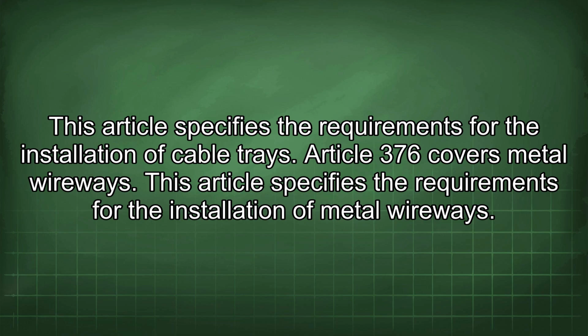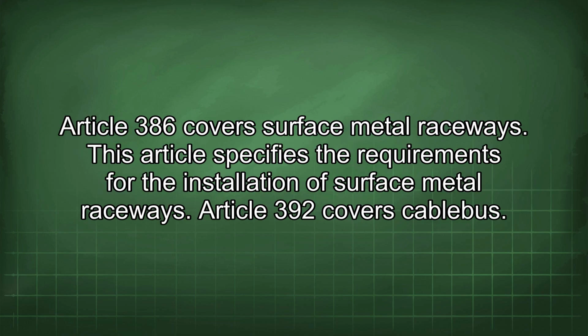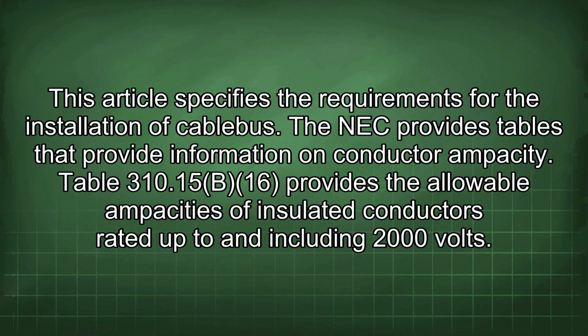Article 376 covers metal wireways. This article specifies the requirements for the installation of metal wireways. Article 386 covers surface metal raceways. This article specifies the requirements for the installation of surface metal raceways. Article 392 covers cable bus. This article specifies the requirements for the installation of cable bus.